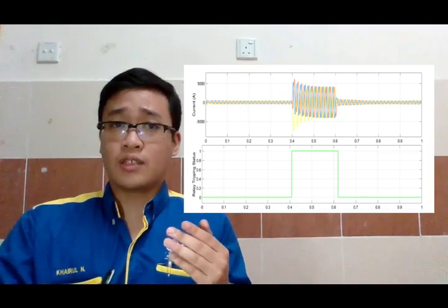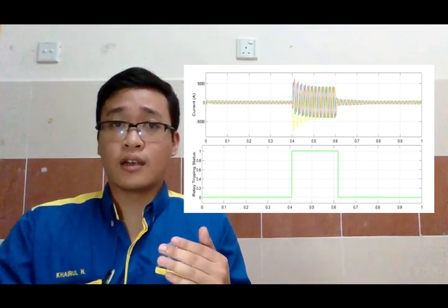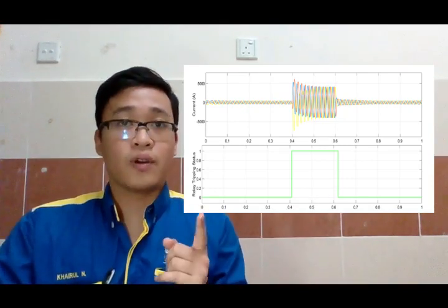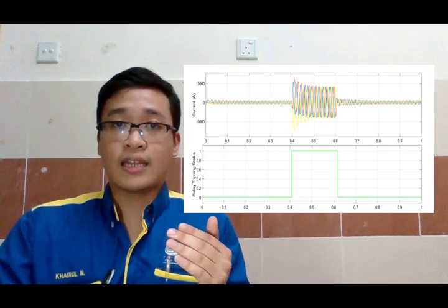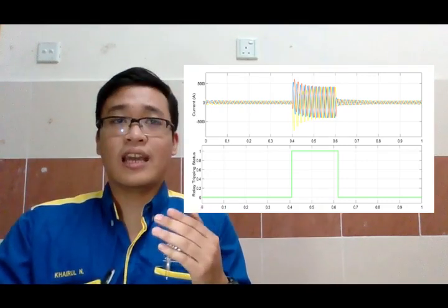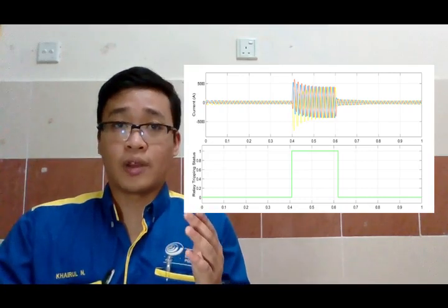Next, another examination involves the analysis of internal faults with zero resistance that occur at the main step-up power transformer located in close proximity to the grid. According to this graph, it can be observed that when a three-phase fault occurs between the time interval of 0.4 seconds and 0.6 seconds, the relay effectively identifies the fault and subsequently generates the appropriate trip signal.